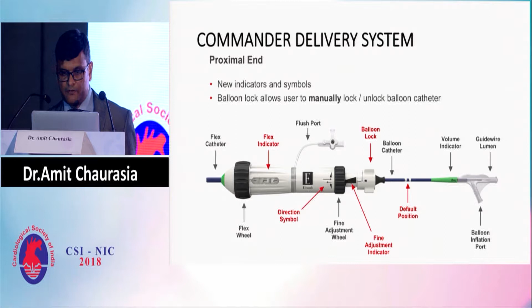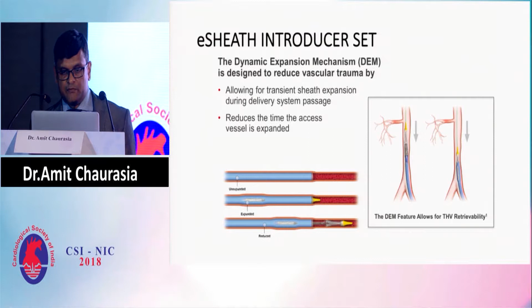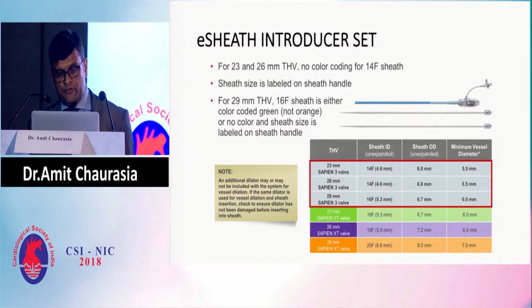The eSheath has a dynamic expansion mechanism by which, if you are using a 29 millimeter, the valve is larger in size than the 16 French, but as you push through the valve, the sheath slowly expands, and as you move forward, it again comes back to the normal size. So this helps not only in decreasing the size of the sheath, but also while retrieving in case you don't want to deploy the valve. This comes in different sizes, and there is no color coding for the 23 and 26 millimeter valve, but there is color coding for the 29 millimeter, which is green.